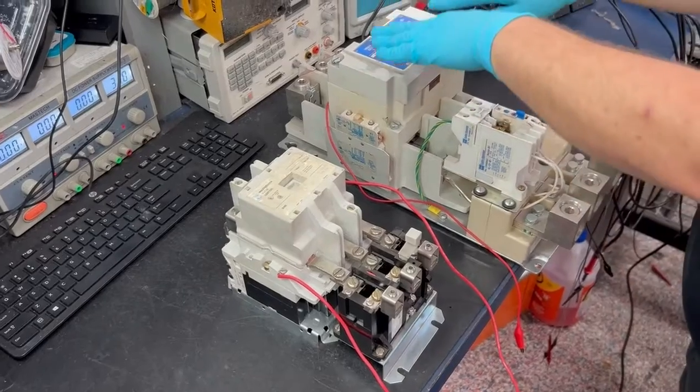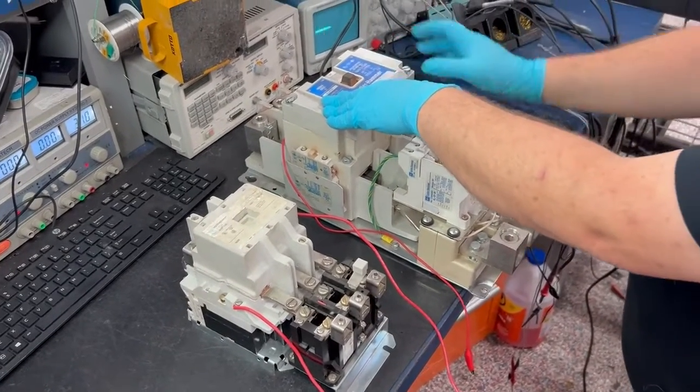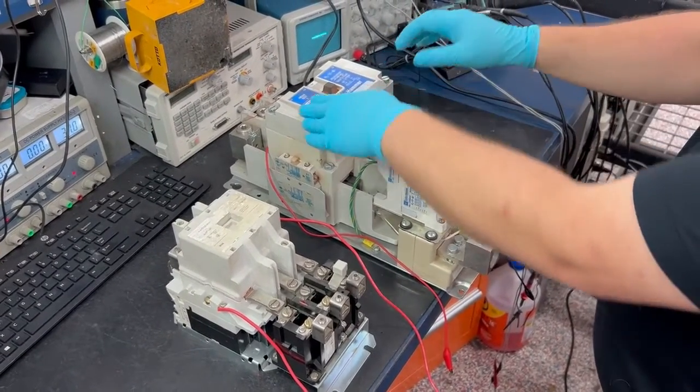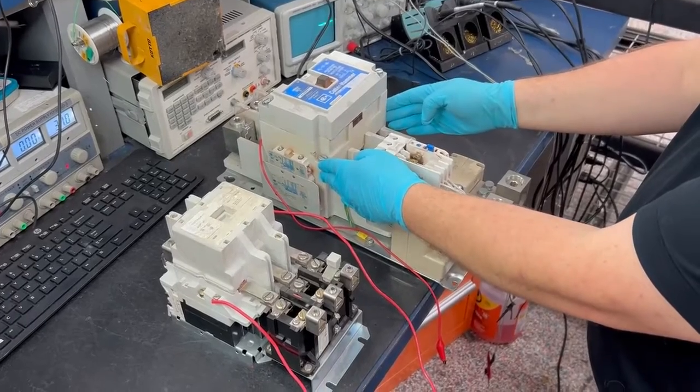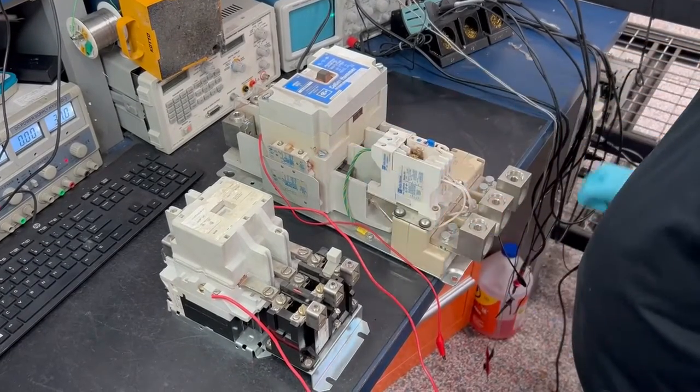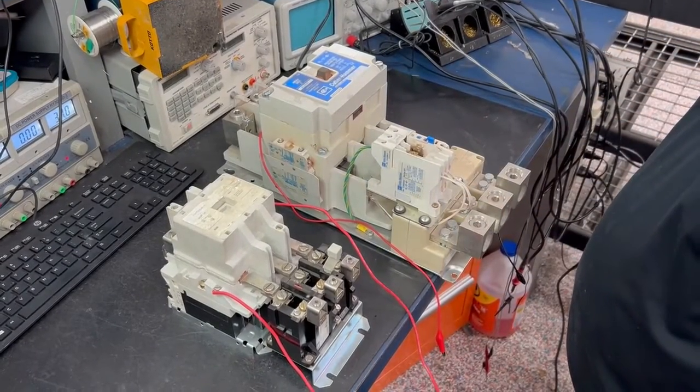This contactor will be completely disassembled, have its coil replaced, have its contacts re-burnished, and we will get it ready to ship to the customer. Thank you for watching.